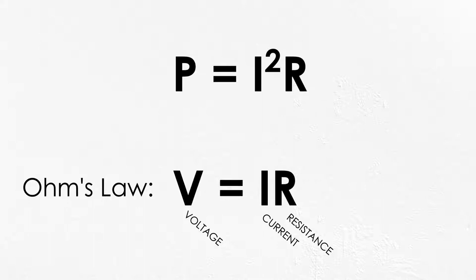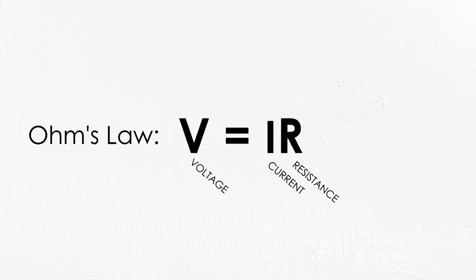So if we want to reduce the losses in a power line, we have two variables to play with. We can reduce the resistance of the conductor by increasing its size or using a more conductive material, but look at what matters more, the I-squared term. Reducing the current by half will cut the lost power to one-fourth, and so on. Going back to Ohm's Law, we can see that the only way to reduce the current and still get the same amount of power is to increase the voltage. So that's just what we do.